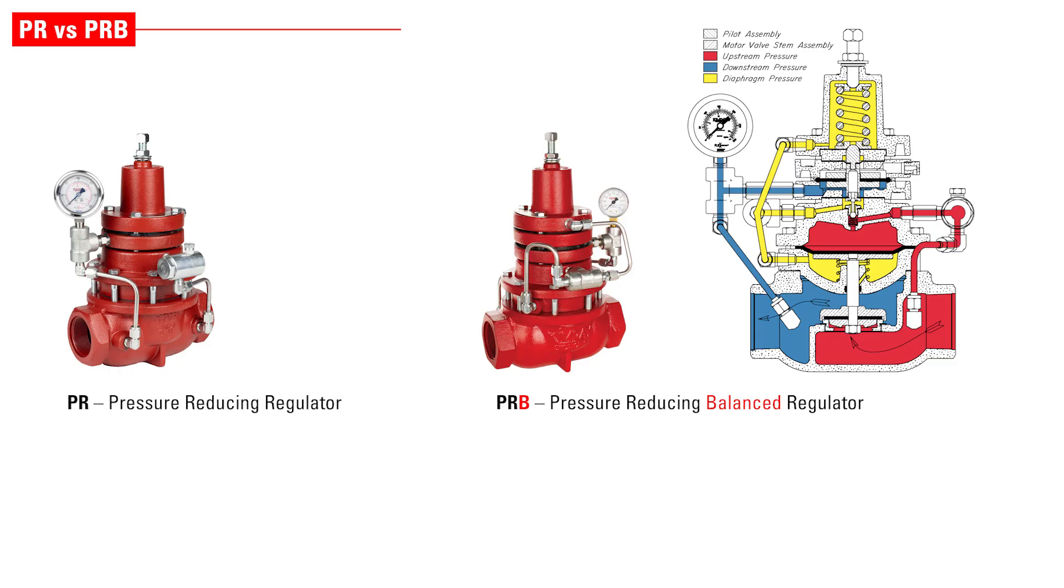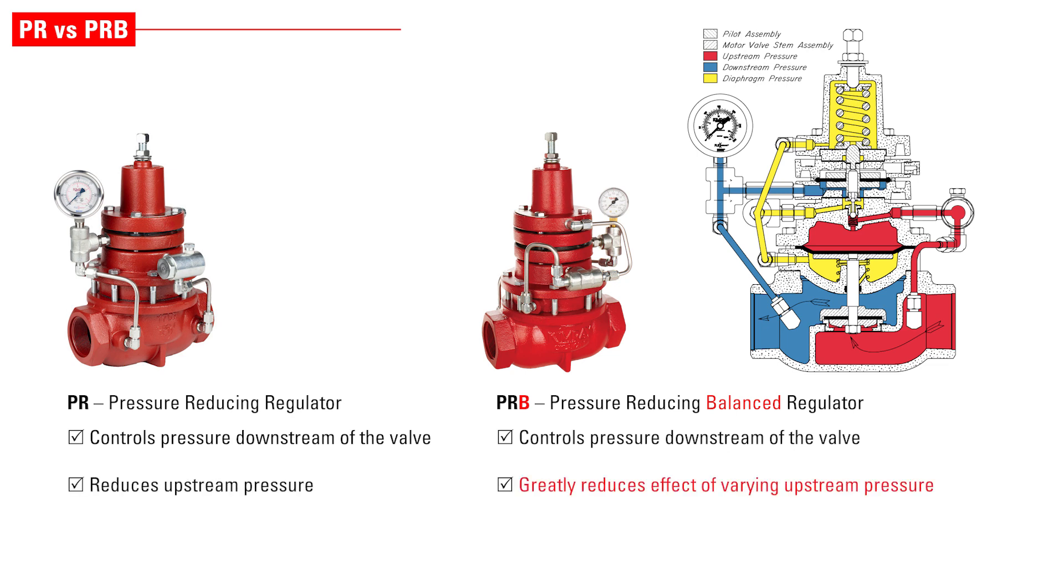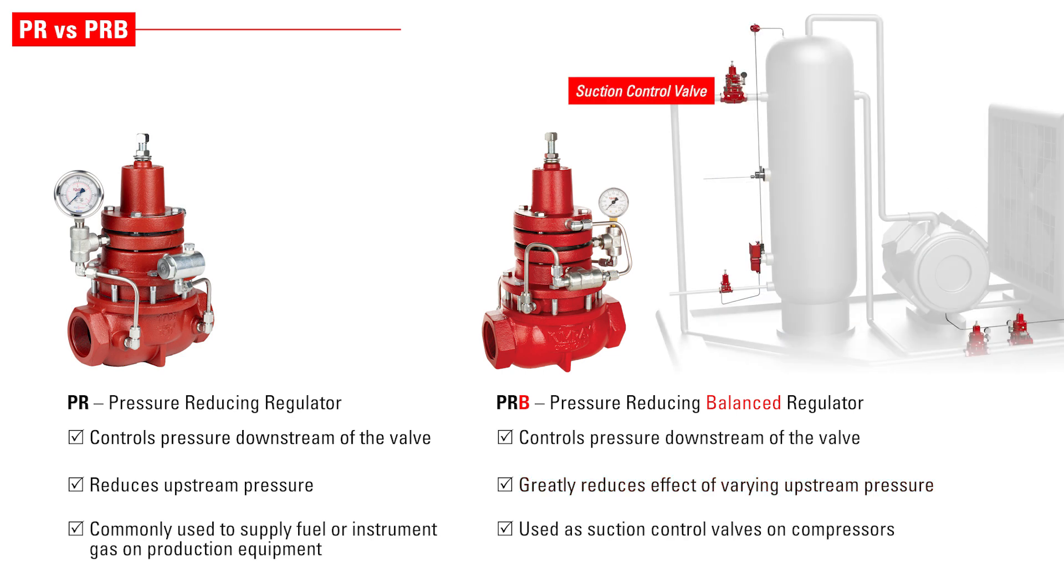A pressure-reducing balanced regulator, or PRB, controls pressure downstream of the valve. The balance feature greatly reduces the effect of varying upstream pressure. These regulators are commonly used as suction control valves on compressors where a higher degree of set point accuracy is needed.